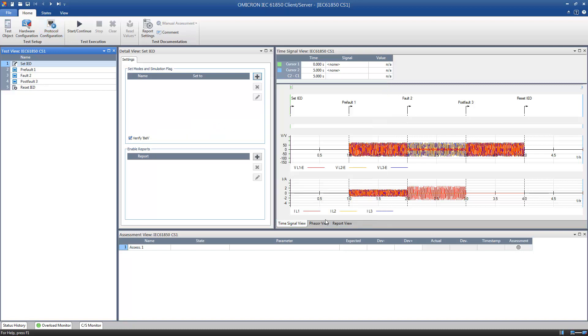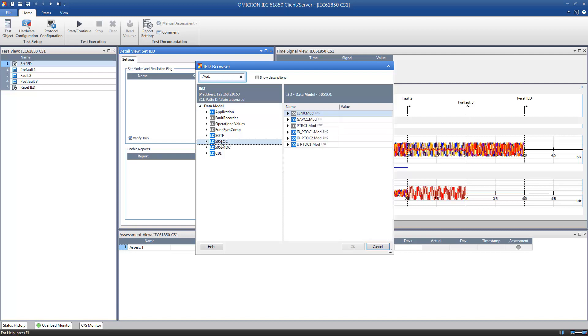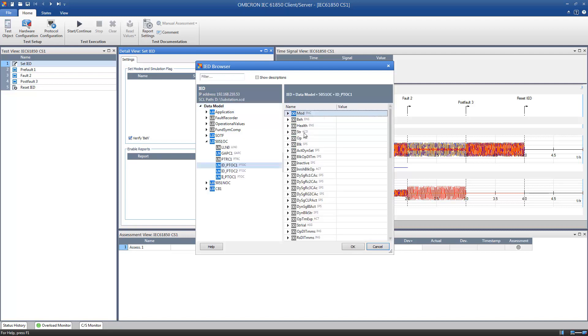We start by defining the state called Set IED. The IEC 61850 Client Server module acts as a client that directly communicates with an IED working as the server. Thus, the module can access the entire data model of an IED for protection testing purposes. In the Detail view, we prepare the IED for the test by setting the mode of the logical node or logical device we want to test.